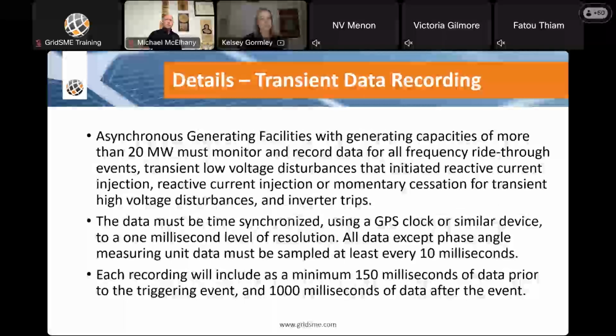Okay, I think this is my last slide, which is transient data recording. This is where most folks get tripped up with Appendix H, which is this requirement at the plant level as well as the inverter level for transient data recording, very fast transient data recording. So each recording will include, as a minimum, 150 milliseconds of data prior to the triggering event and 1,000 milliseconds of data after the event.